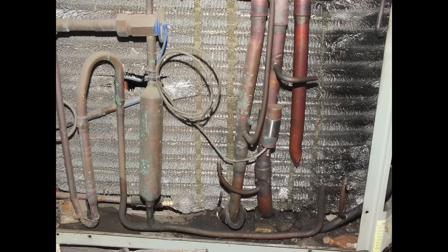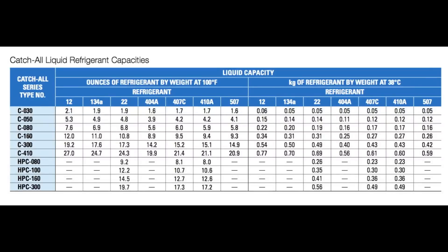Here's a Sporlan chart showing dryer refrigerant volumes. The C160, which is a 16 cubic inch dryer, holds 10.8 ounces of R22, and the 080 right above it is 6.8 ounces. So if there was no dryer in the unit and I added a 16 cubic inch dryer, I'd add 10.8 ounces. Or if it was R410A, I would add 9.4 ounces. This is what you'd add if you're adding a dryer where there was none before. Otherwise, you have to subtract what you estimate the original factory dryer held from the new one.